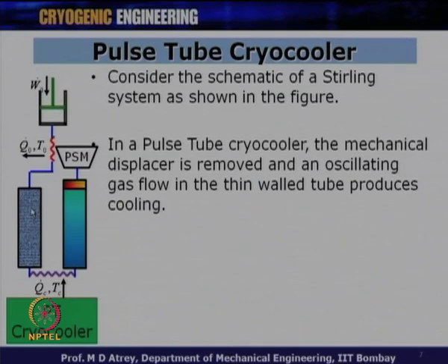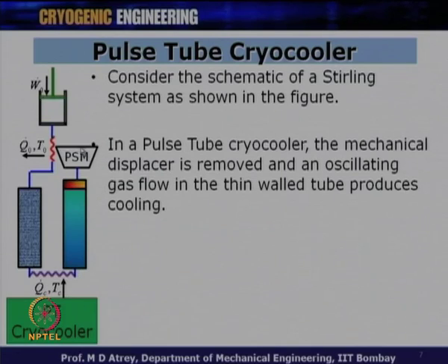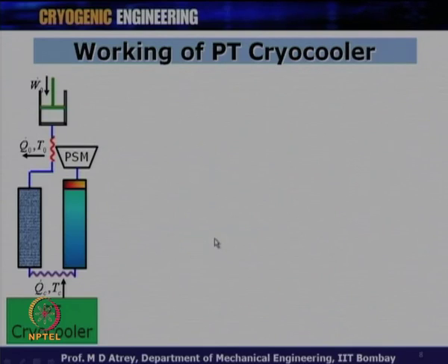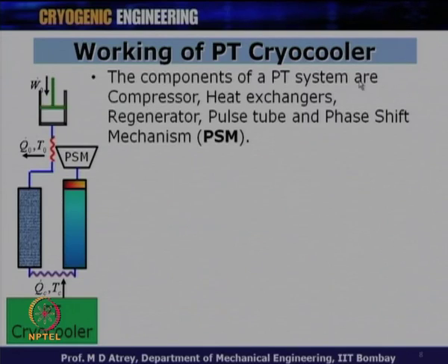In effect, we have a regenerative cryocooler where oscillating pulses enter a tube subjected to pressurization and depressurization, generating cold. This gas tube is called the pulse tube and this phenomenon is called pulse tube action. The components of a pulse tube system are: compressor, heat exchanger, regenerator, pulse tube, and phase shift mechanism (PSM).